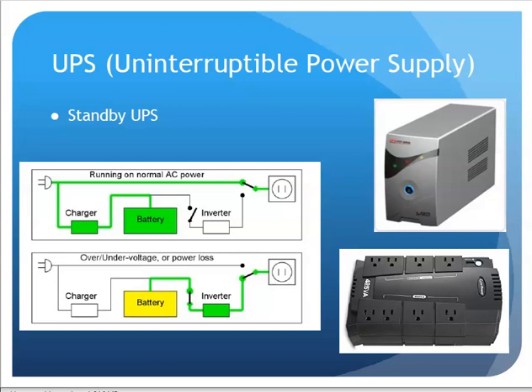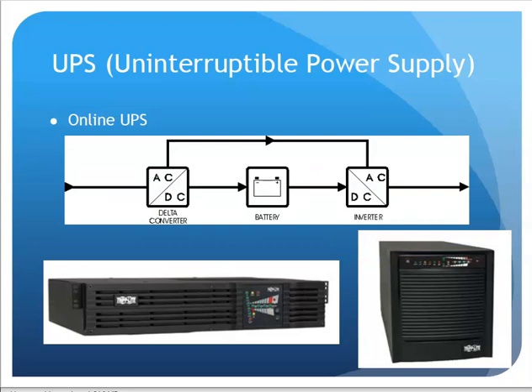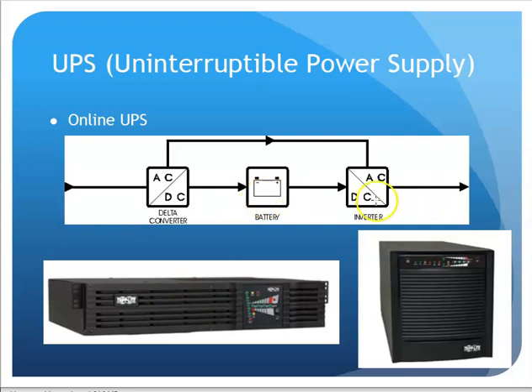The other style is an online UPS, which is usually more expensive — similar to what we have bolted in our lab room server cabinet. With an online UPS, the power is continuously charging the battery, and the devices are being fed from the battery at all times. It's similar to your laptop charger: when plugged in it charges the battery, and when unplugged the laptop still runs from the battery. Online UPS units don't have that switchover time, making them more reliable for sensitive equipment.